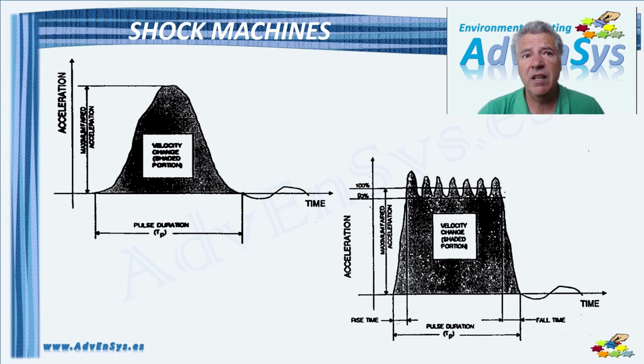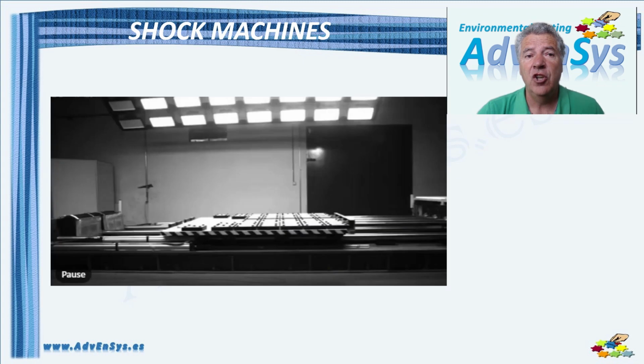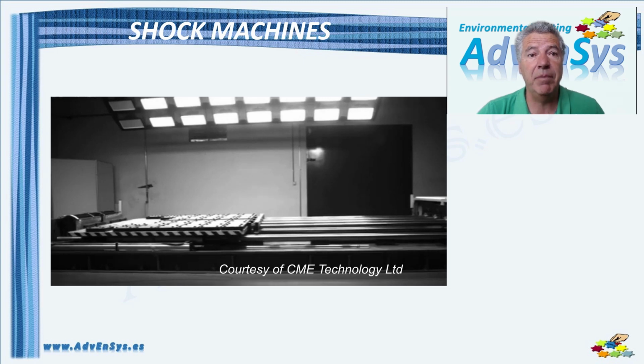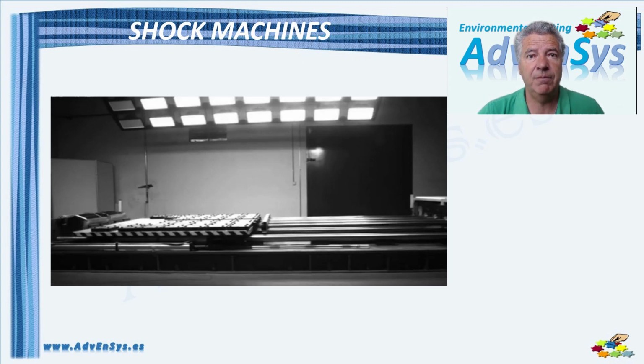The type of results we get with a shock machine are normally not too precise. The waveform is not clean, typically with significant ripple, and the repeatability is questionable. However, there are high-level pulses that can only be generated by the use of a shock machine. Shocks can be performed in vertical or in horizontal axes, as we see in the video below for battery testing.